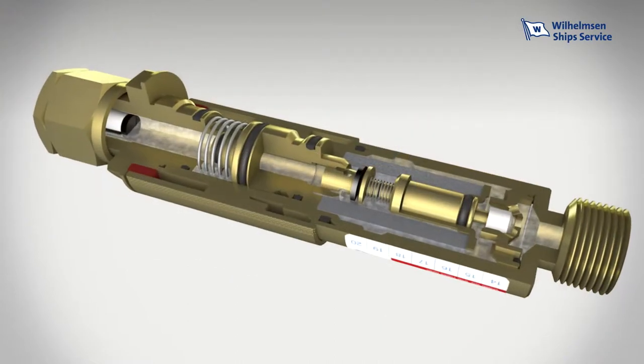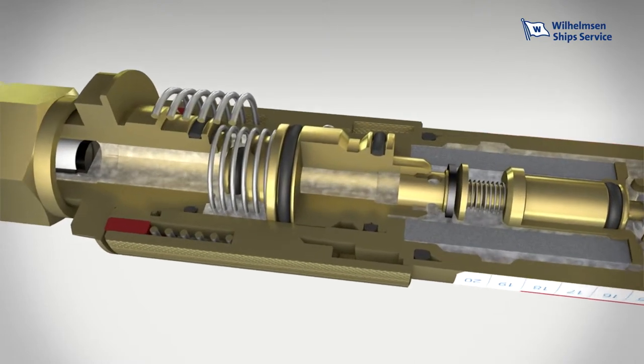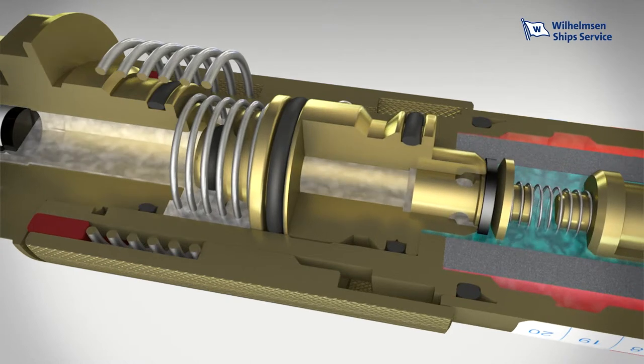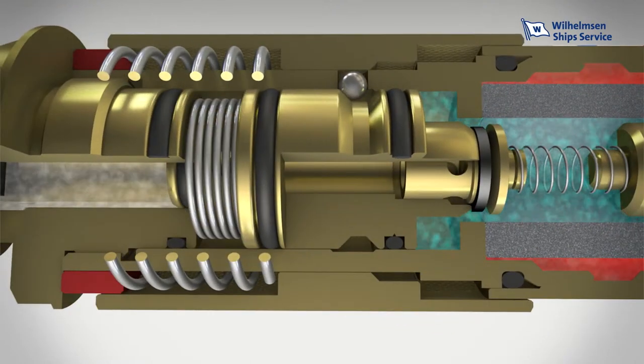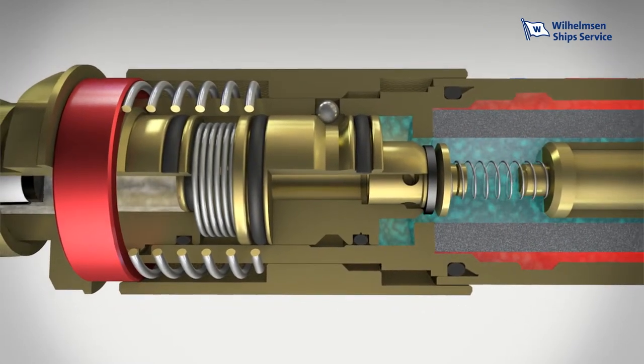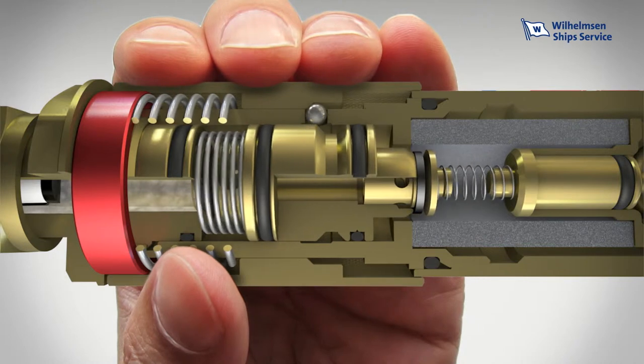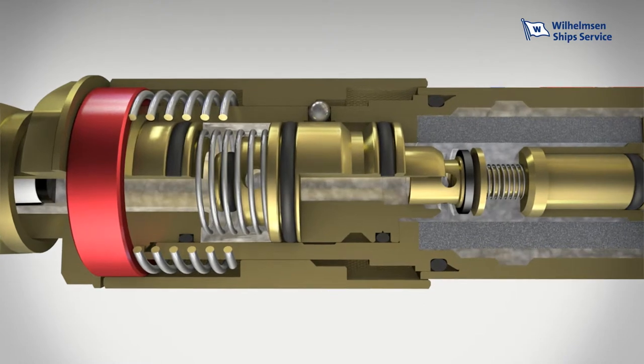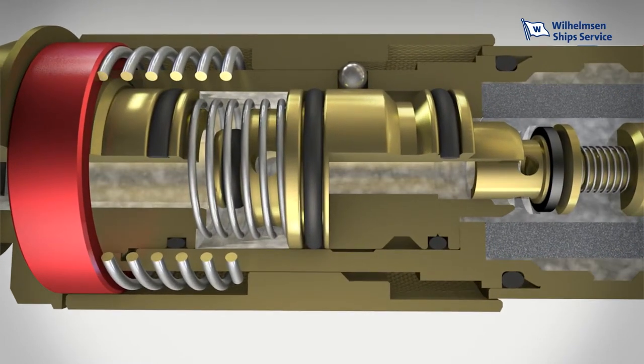For maximum safety, Unitor also provides a pressure-sensitive cut-off valve for various models. This fourth protection element activates in the event of a flashback and interrupts the gas supply permanently. A red alarm mark makes every single flashback visible. The gas flow is only opened after manually resetting the cut-off valve. This method ensures that no dangerous situation remains unnoticed and prevents the safety device from potentially heating.